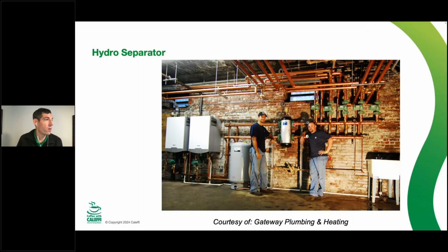So if we were going to do this and add closely spaced tees, we would have to take a lot more real estate in this mechanical room. This is a very luxurious size for a mechanical room. When I worked in Colorado as a manufacturer's rep, this is bigger than 99% of the mechanical rooms that I was in, even if they were moving more BTUs and had more boilers in and out of that space. So this really made that task a lot more compact.